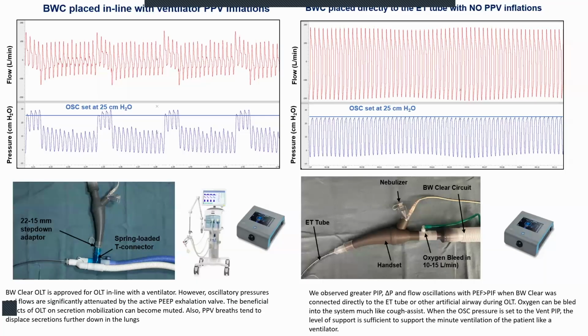And then what we showed is if we were to remove the patient from the ventilator and apply it directly to the endotracheal tube, and we bleed in oxygen at, say, 10 or 15 liters a minute, we're able to observe these higher flows, and you get more of that flow bias, right? So this is down around 205, and this is down around 190. More of the oscillation pressure, obviously, is going to be transmitted to the patient, even through the endotracheal tube.